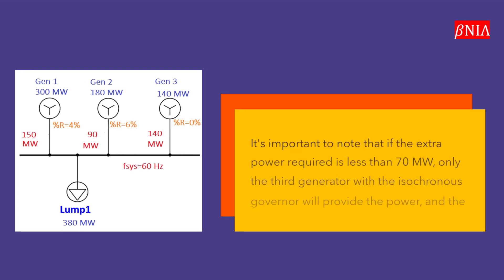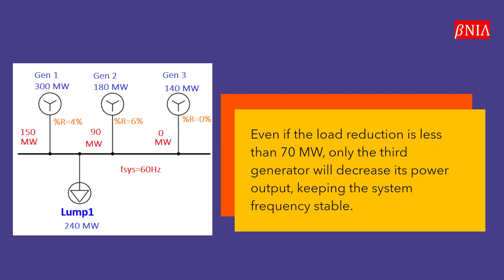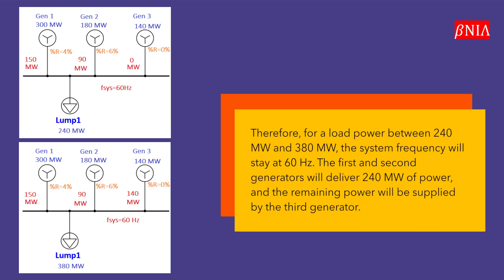It's important to note that if the extra power required is less than 70 MW, only the third generator with the isochronous governor will provide the power, and the system frequency will remain at 60 Hz. Even if the load reduction is less than 70 MW, only the third generator will decrease its power output, keeping the system frequency stable. Therefore, for a load power between 240 MW and 380 MW, the system frequency will stay at 60 Hz. The first and second generators will deliver 240 MW of power, and the remaining power will be supplied by the third generator.